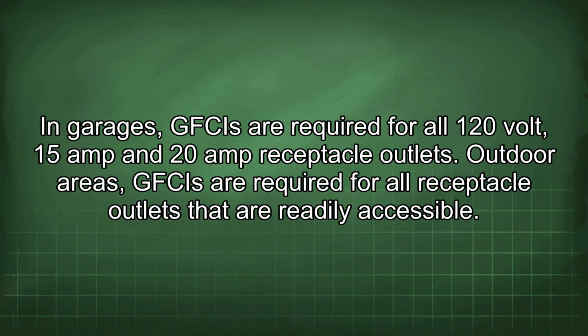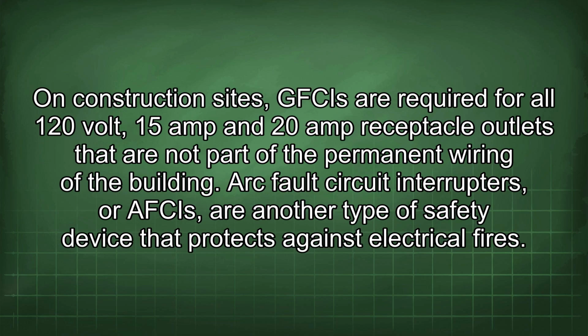In garages, GFCIs are required for all 120-volt, 15-amp, and 20-amp receptacle outlets. In outdoor areas, GFCIs are required for all receptacle outlets that are readily accessible. On construction sites, GFCIs are required for all 120-volt, 15-amp, and 20-amp receptacle outlets that are not part of the permanent wiring of the building.